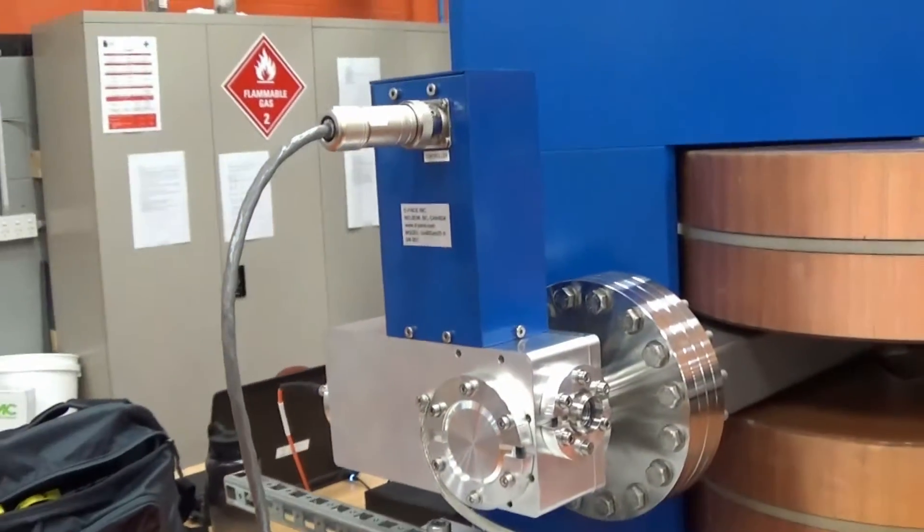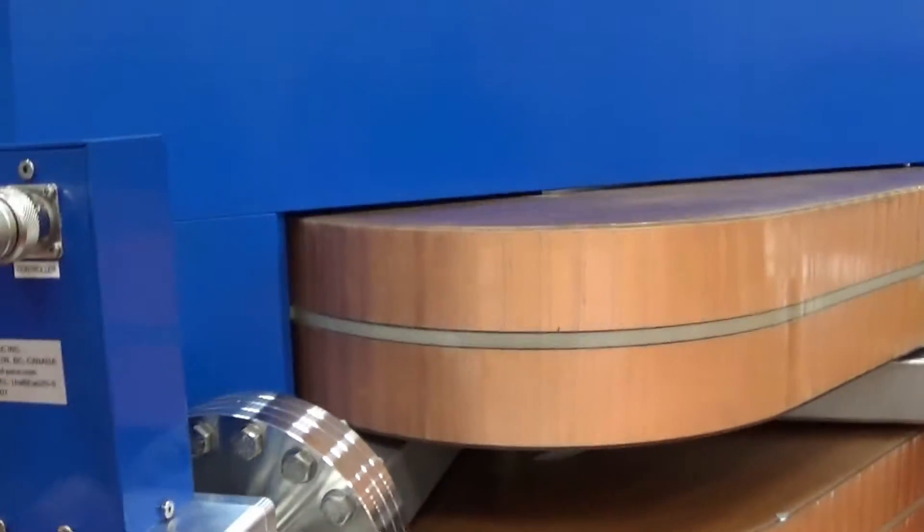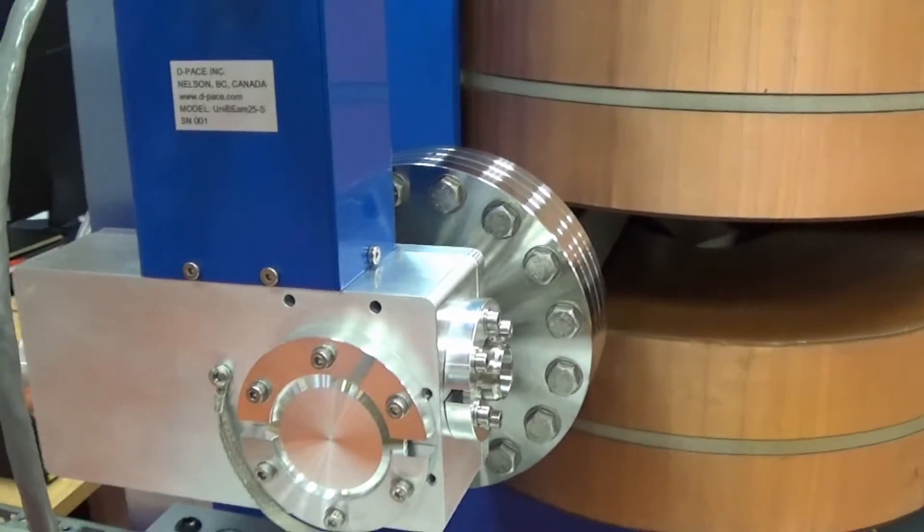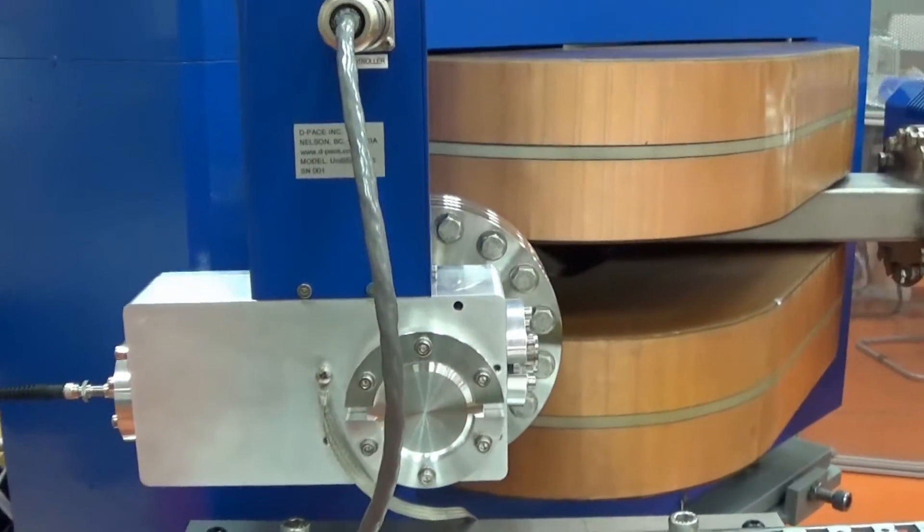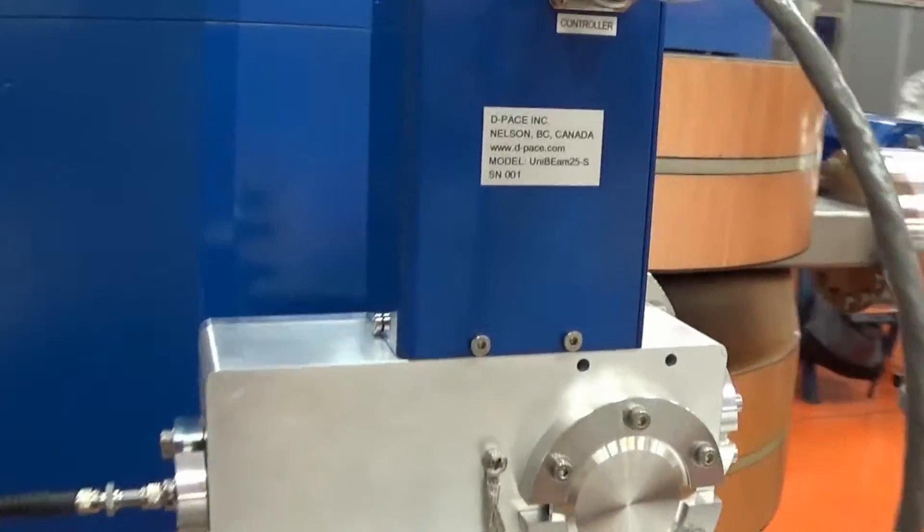This little guy here is an optical wire scanner. It has a piece of fiber optic fiber that moves back and forth in the beam. It fluoresces and we can measure the light coming out of it and get a profile of the density of the beam. It's a new product under development.